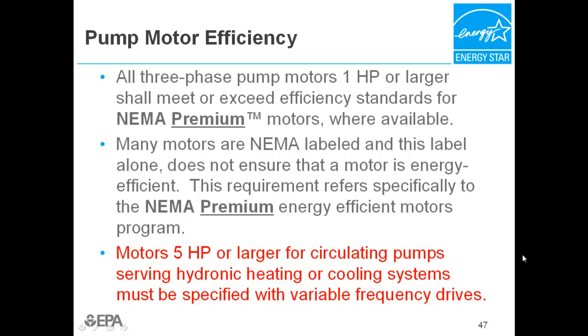In addition, for buildings following the prescriptive path that have hydronic heating or cooling systems, any motors 5 horsepower or larger for circulating pumps serving those hydronic systems must be specified with variable frequency drives.